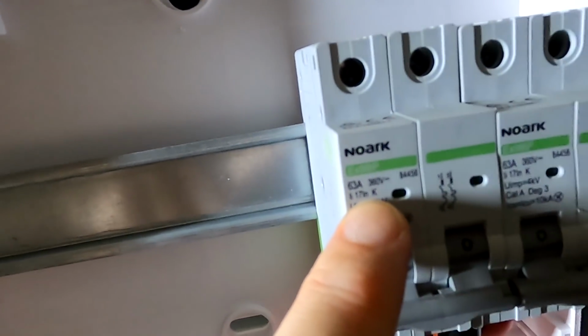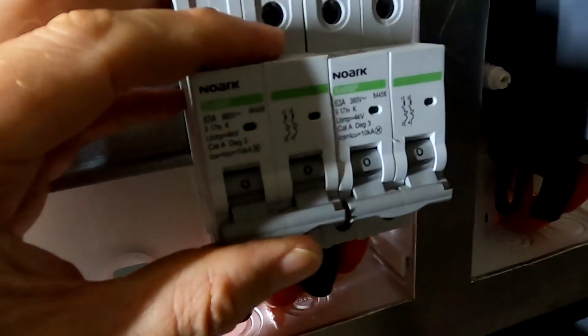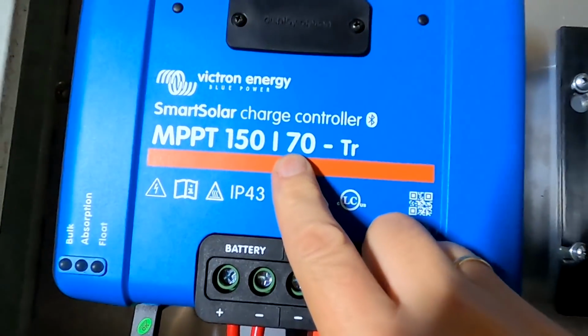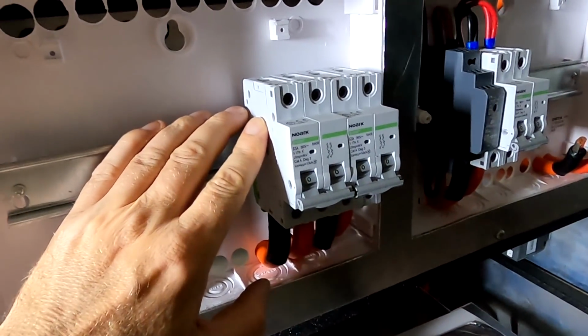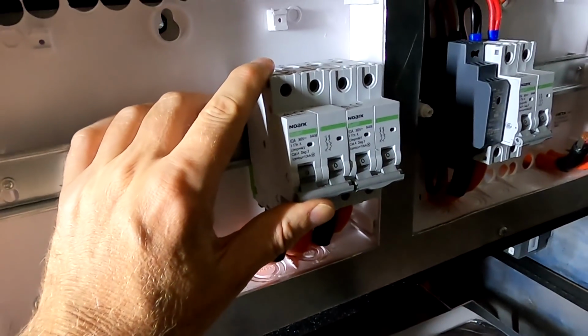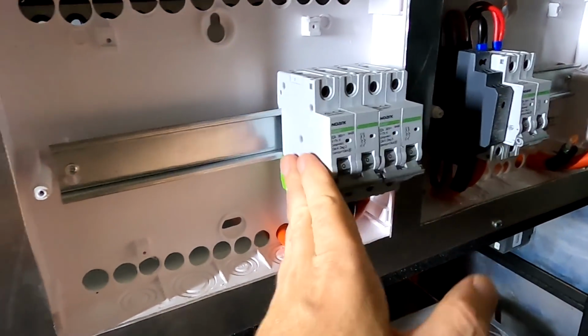until we're upgrading the solar on the roof. Because, as you can see, these are 63 amp DC circuit breakers, isolators, positive, negative. It's only 63 amps, right? And the charge controllers can do 70 amps. So we are 7 amps short. And if we run them on 65 or even 70 amps for longer periods of time, they're getting really hot. And obviously, eventually, they will trip and disconnect our solar, which is not ideal.